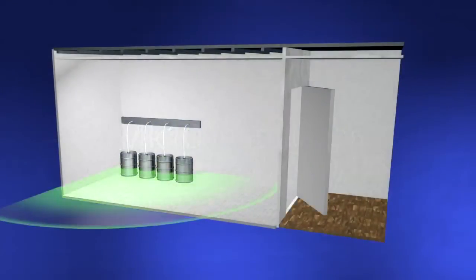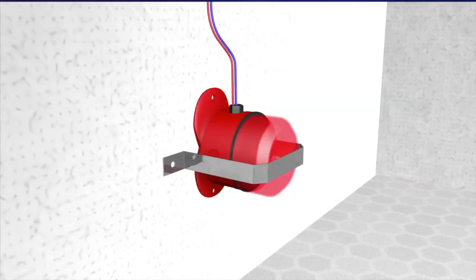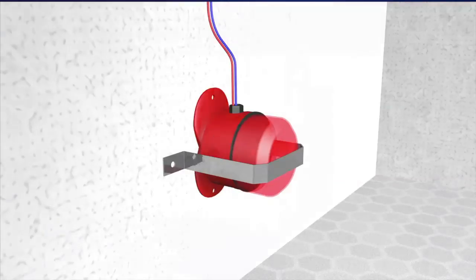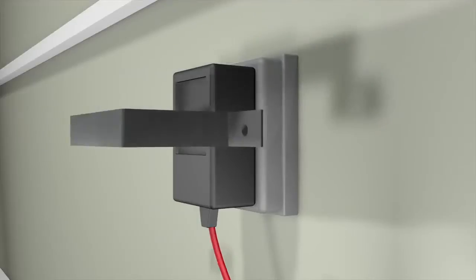When you have found a place for mounting the sensor that is within the stipulated 15 feet or 5 meters from the distribution point, you can use the box that the MK10 was delivered in to find the correct height that the sensor should be mounted at, that is to say, 12 inches or 30 centimeters from the floor to the bottom of the sensor. The box is 12 inches long. Mount the protection bar over the sensor so that it does not get damaged. Try and route the cables in cable ducts on the wall up over the ceiling to a power outlet and to the horn strobe that is mounted outside the room or the danger zone. The yellow sign for the MK10 sensor should be mounted in a permanent fashion above the sensor. The sign for the horn strobe must be placed next to the horn strobe. Don't forget to mount the plug lock on the power supply in order to avoid tampering.